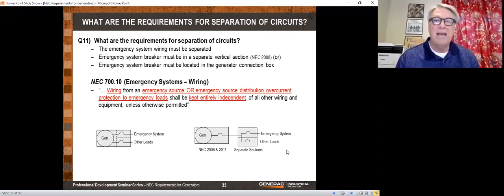You must have metallic isolation between the emergency circuit breaker and the other circuit breakers, because if that other circuit breaker blew up, it could take the emergency breaker out. And so you have to isolate those two. So Generac met that by redesigning all their generators.